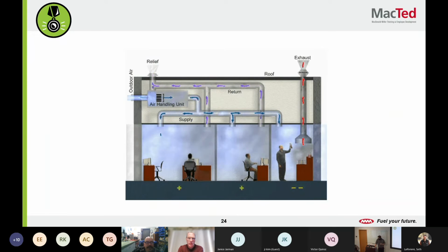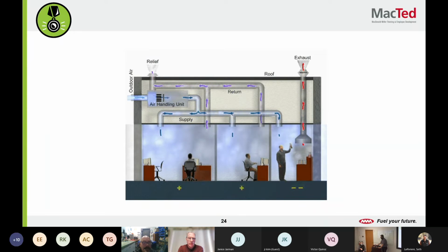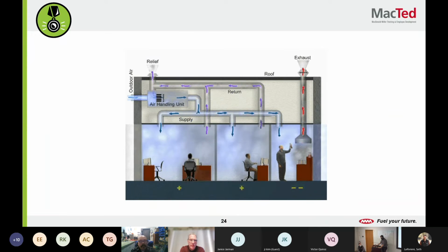No. Oh, I was gonna say too, with this, this is another thing where when we were talking about how buildings are, like the airflow is designed, we have a certain amount of air that comes out of these vents and then a certain amount that returns. Like in a lot of the lab spaces I'll work in sometimes, they have to maintain a positive pressure. So I mean, like our test and balance department goes out and they have to say, 400 CFM in, 370 CFM out, where they have to measure it and make sure each of those spaces are pressurized. So if you have a space that's depressurizing or used to work but isn't, a lot of times a damper might fail, it might not open when it should have. So that's a common one that you might have come across too, dampers fail, stuff like that. So building pressure is huge, and the more you get into it, the more you run into pressure issues.